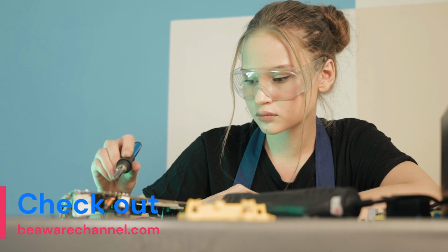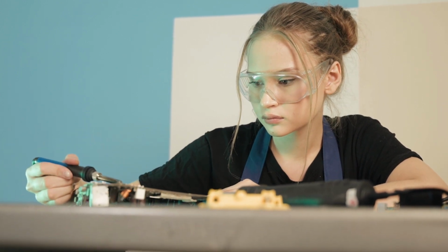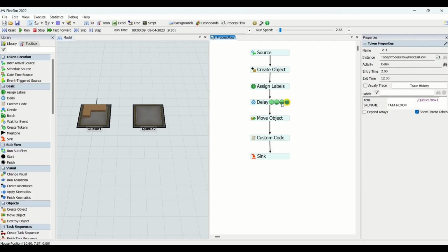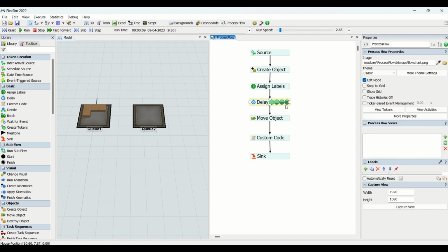So with the help of the digital twin emulation, we can validate the PLC logic which is created, whether it is actually working the same. We can also create a PLC logic in a process flow, and we can explain that or show it to a PLC engineer, who can then create a PLC ladder logic in their own software by watching the actual process on a virtual platform.